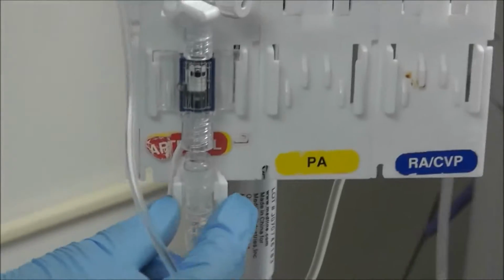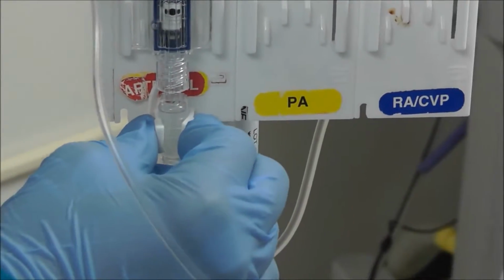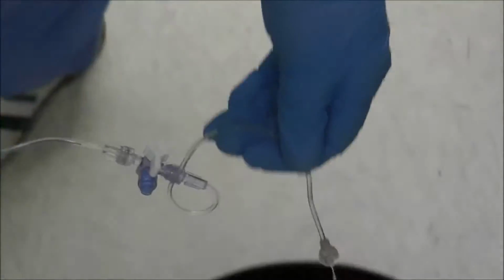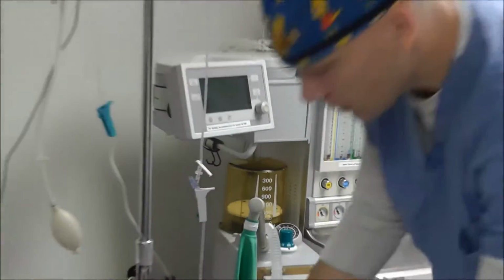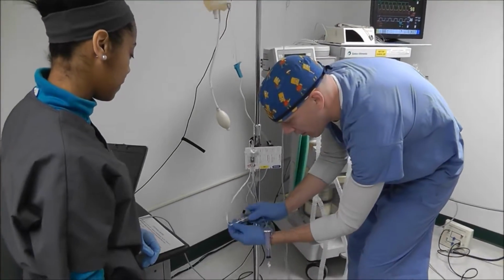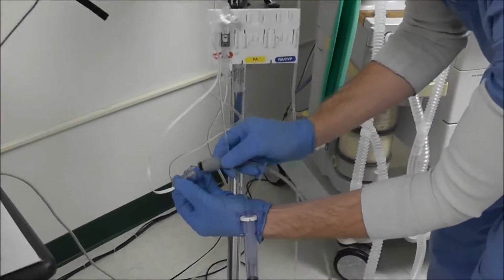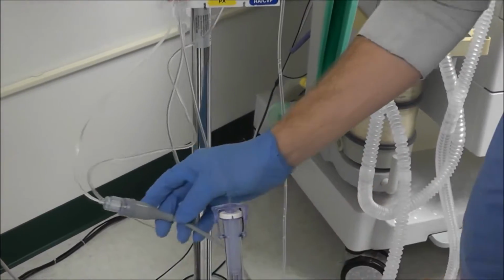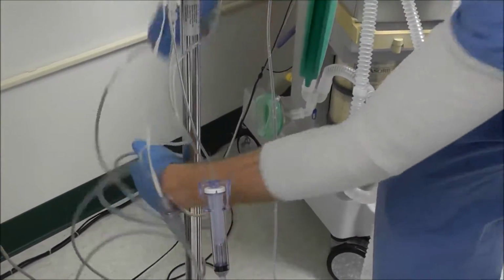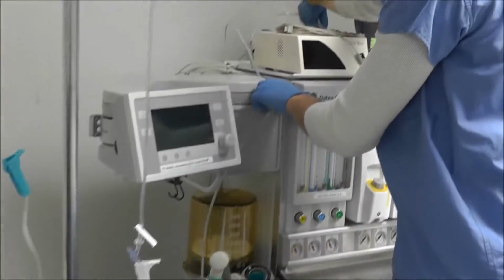Here's how you flush it. Push. Push in, and allow all the air to come out of your tubing. Okay, and we see that all the air is out. We have flushed the A-line. We're almost done here. The only thing that we need to do now is we just need to come down here and actually connect the transducer cable to the transducer, and then plug it up into our monitor up here, okay?